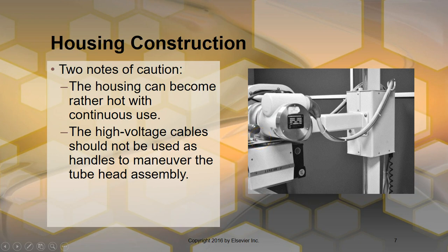So don't grab the cables when you want to move the tube, and don't let the patients grab the cables. Sometimes your patient will say, I've got to get up, and they just start reaching. And if these cables are hanging down a little bit, they'll want to grab them. They've actually gotten better over the years about making these a little different, where they go upwards instead of hanging down. So that's a really good thing.